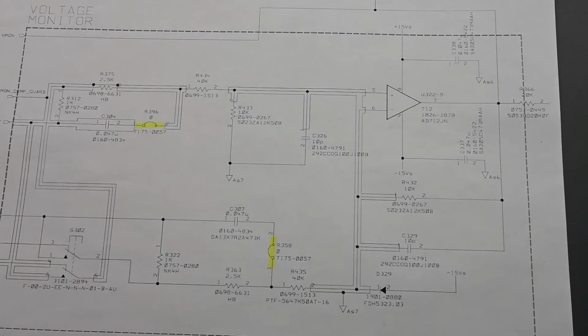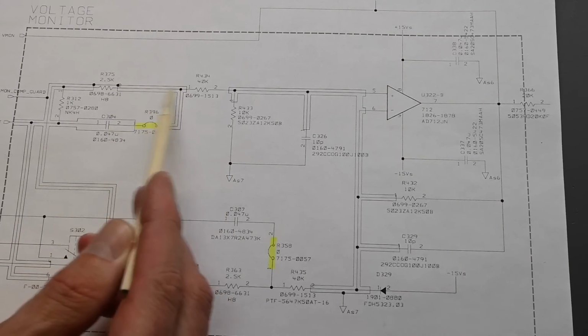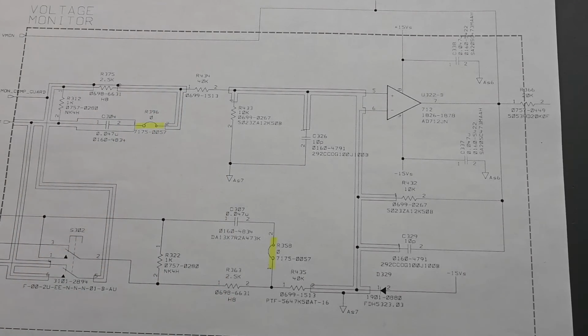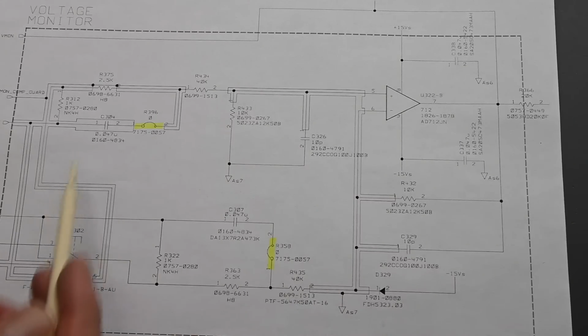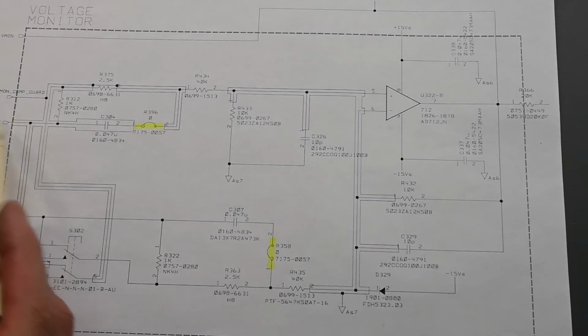The reason guard traces are used is because this power supply is able to measure extremely low currents, and if you have any basically leakage on the circuit board, it can affect those readings. And the guard trace is basically, as the name implies, it guards the main trace from noise and other types of interference and problems. So, this can measure down into the microamps of current, and they want that very, very accurate. So it has all these guard traces in all the critical circuits. Also helps with the stability, the voltage reading, and so forth. These are the voltage sensing lines. So they're used extensively on the board.